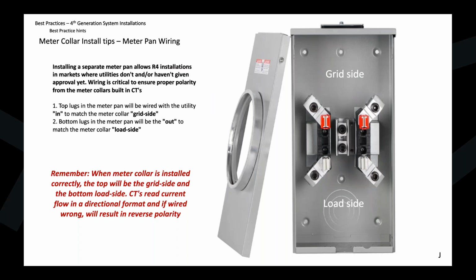But what we've seen when electricians are installing this, they actually bring the grid side in the bottom, which is making the current flow from bottom to top, which is then going through those current transformers within the meter collar the opposite direction, which is obviously causing errors, showing negative numbers, and we absolutely do not want that.